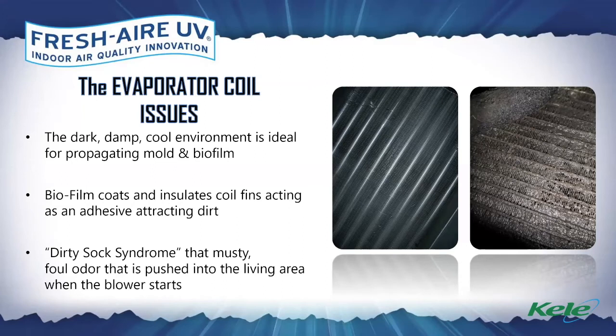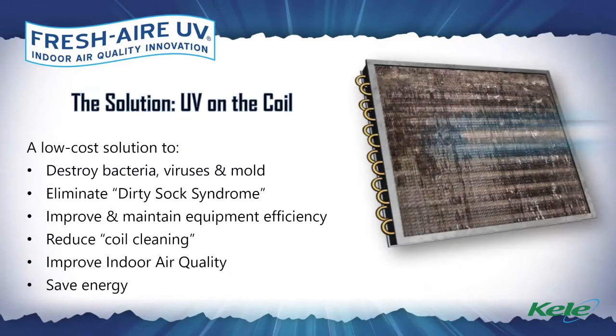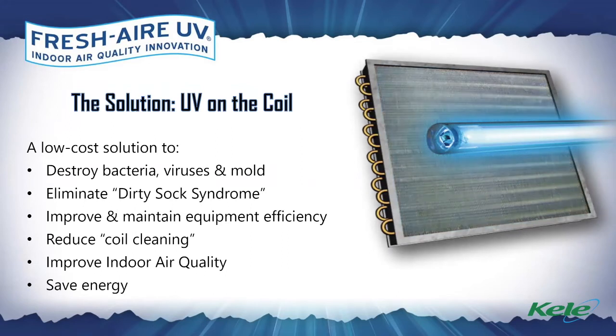So what we always like to promote is mounting a UV system on an evaporator coil inside the air handling unit. And of course, besides treating the biologicals and treating the air, we're also addressing the equipment itself: improving equipment efficiency, improving heat transfer, improving airflow, reducing wear and tear. The system does not have to work as hard, and it is a great solution and a green solution to keep the equipment running to spec.